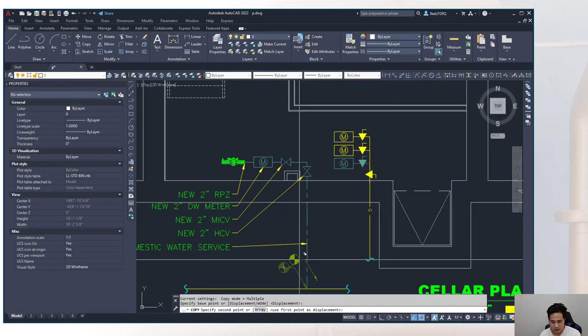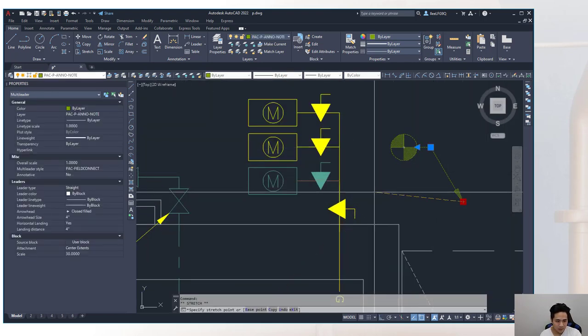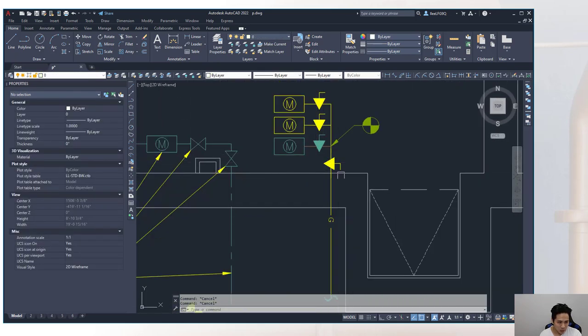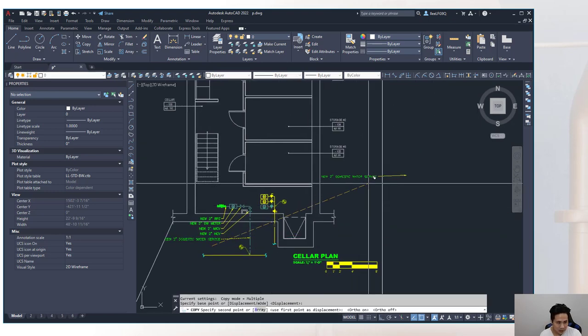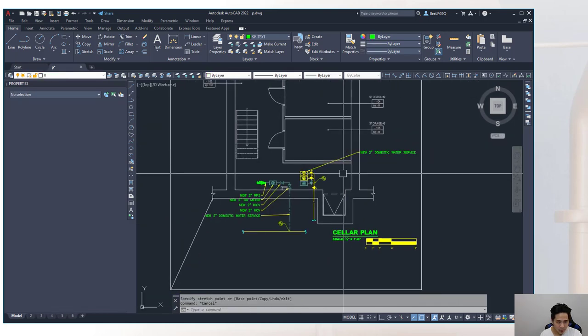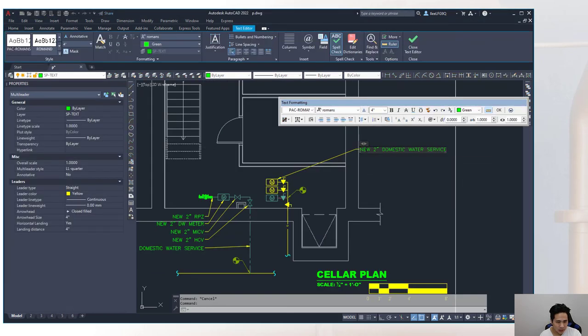The note covers the fact that all piping is diagrammatic — for example, stacked meters are shown offset for clarity rather than on top of each other. The piping should still be drawn close to where equipment will actually be installed. Next, draw the water heaters: three heaters, one per unit, located in the mechanical room near the chimney.